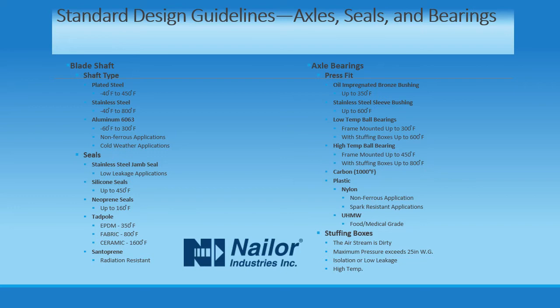Seals can make or break the performance of the damper in the field and are determined by performance requirements. Our industrial products come with optional blade and jamb seals. Jamb seals are usually made from stainless steel and prevent leakage between the ends of the blade and the damper frame. In cases where the duct medium must be contained with zero leakage, axle seal options such as double gland stuffing boxes — a packing gland impregnated with graphite — and O-ring axle seals ensure isolation of a dirty air stream. Blade seal materials range from neoprene for mild temperatures to silicone, EPDM, fabric, and ceramic tadpoles all the way up to 1,600 degrees. We have also worked with Santoprene radiation-resistant seals on dampers for nuclear projects for the Department of Defense.